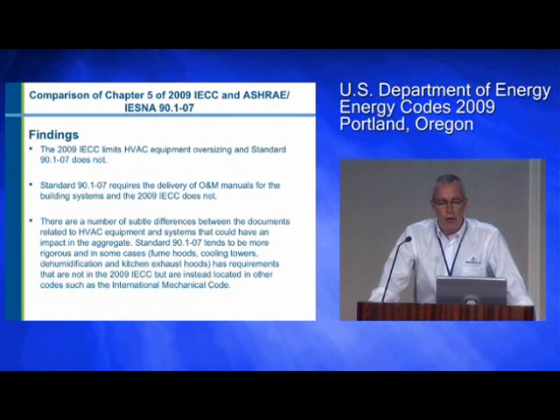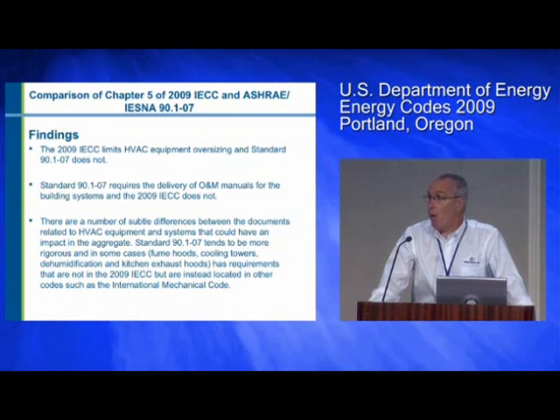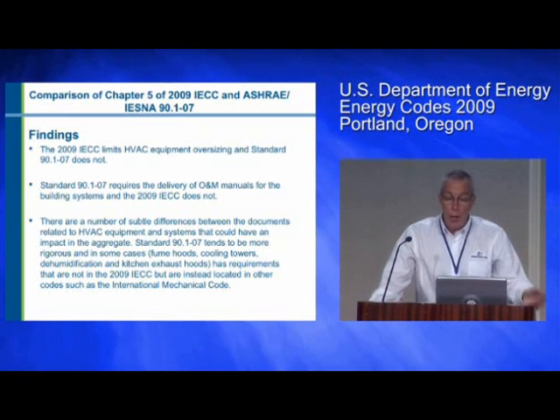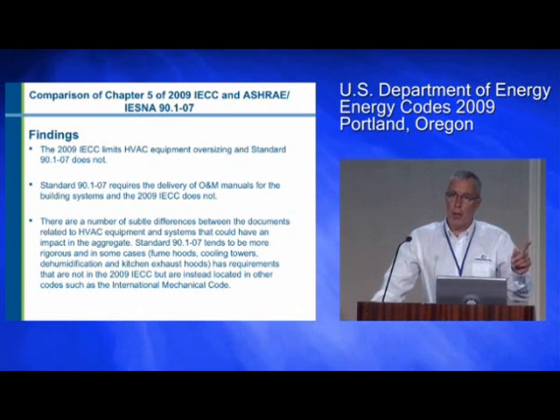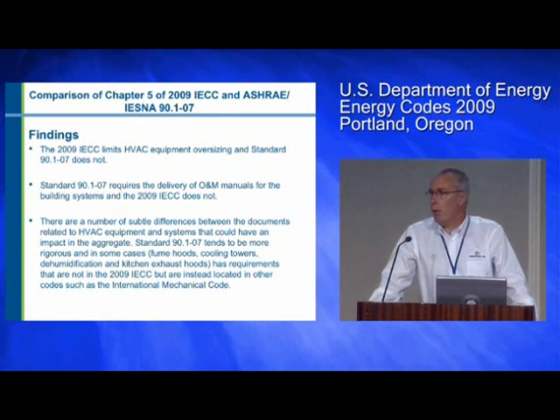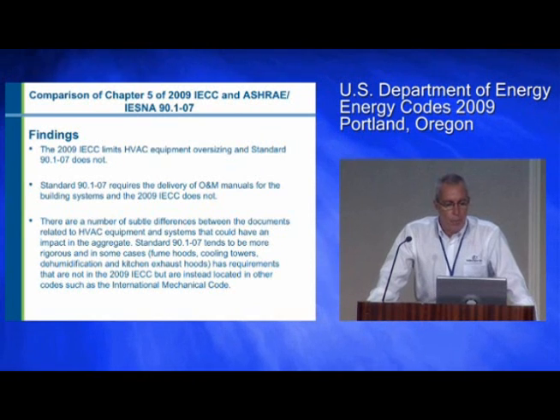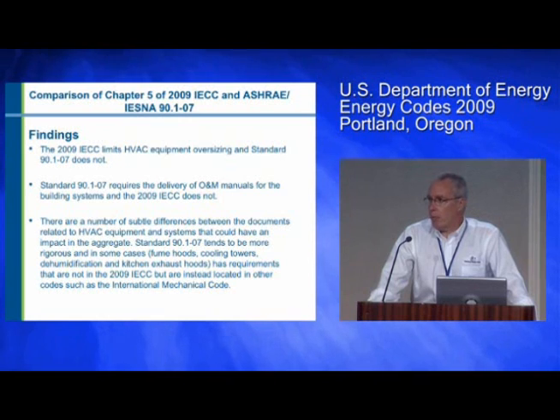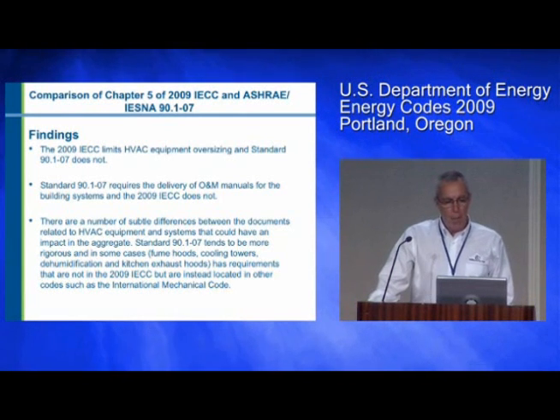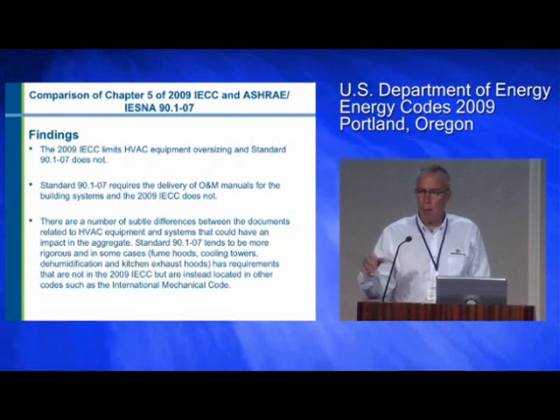The IECC limits HVAC equipment oversizing, 90.1 doesn't. They both say to calculate loads, but 90.1 doesn't tell you what to do once you've calculated the loads. Calculate the loads, fine. But the IECC says not only calculate the loads, but we want the equipment sized to those loads. 90.1 requires the delivery of an O&M manual for the building systems. You get a car, you get an owner's manual in the glove box. The IECC does not. And there are a number of subtle differences.